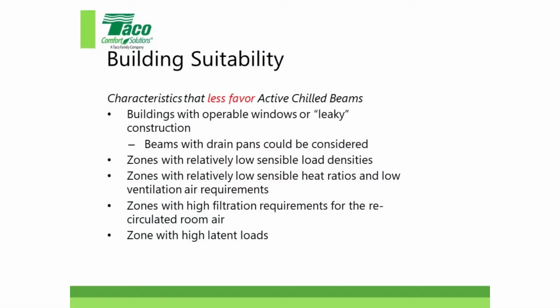Here's a few that are less favorable. And I can't emphasize the first one enough. Old buildings, leaky windows, leaky construction. If there are ways for humidity to get into the building, that's not a good situation for one of these types of systems. Stay away from it. Go back to your more traditional type of system. This gentleman was talking beforehand, he's in San Diego, maybe not in his area, it's not as critical, but if you're in a humid climate, that's a big disadvantage, a big issue. And then if you have a relatively low sensible density, that could be another reason not to use this. So you want to be around 70% in that regard.